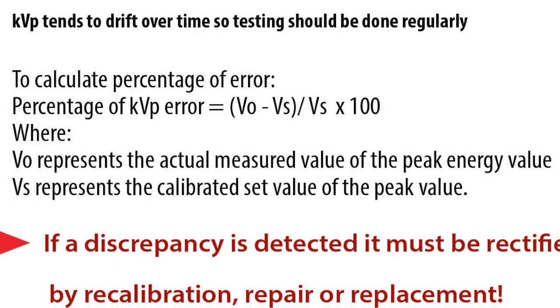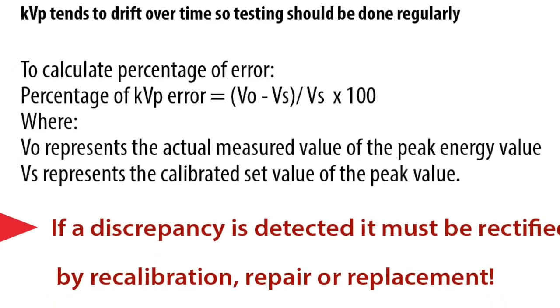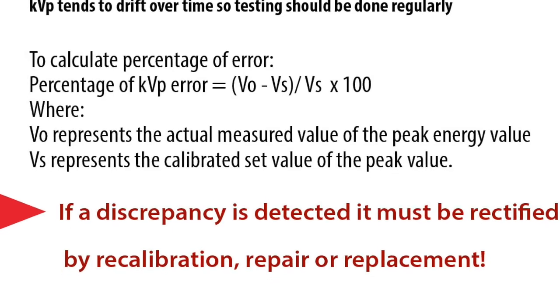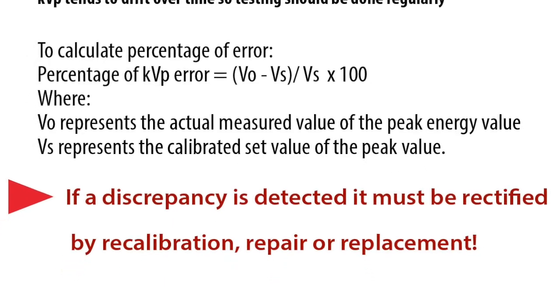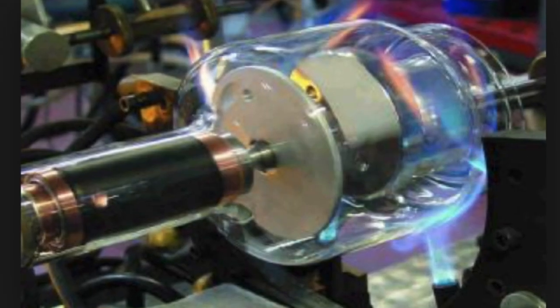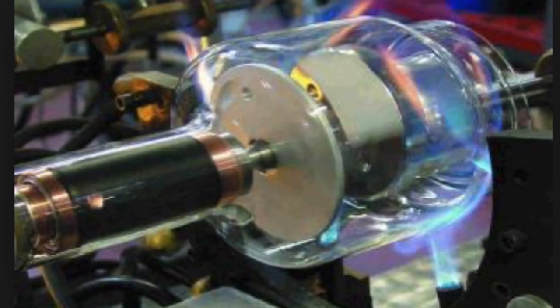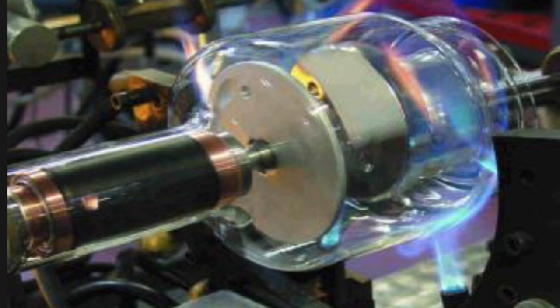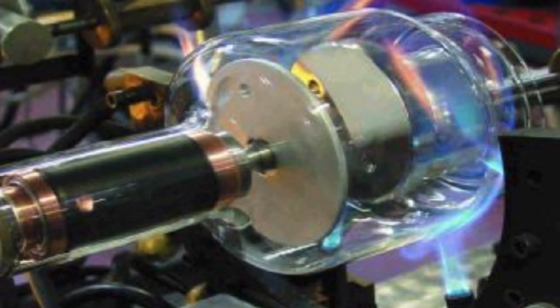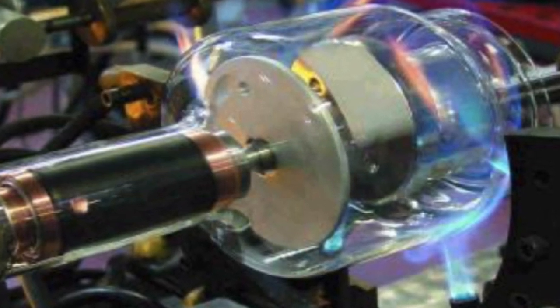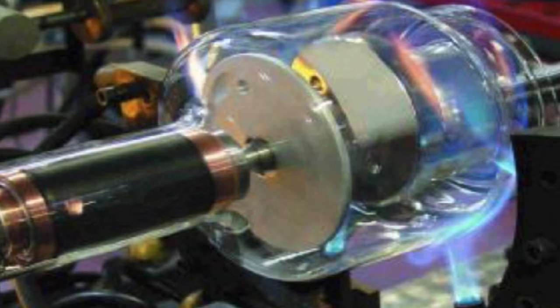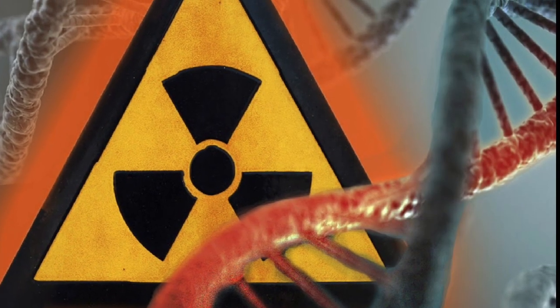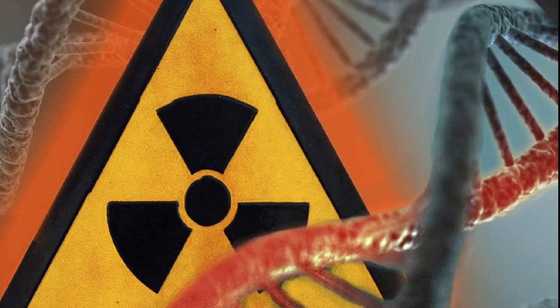If a discrepancy is detected, recalibration should be performed to correct it if possible, or otherwise repair or replacement of the tube may be necessary. Milliamperage levels also often change slightly over time as a result of the aging tube. Therefore, these levels also need to be routinely checked. Not only will a deviation affect receptor exposure levels and thus image quality, it is of utmost importance to safety as it is directly proportional to patient dose.